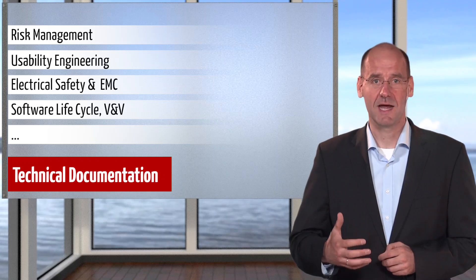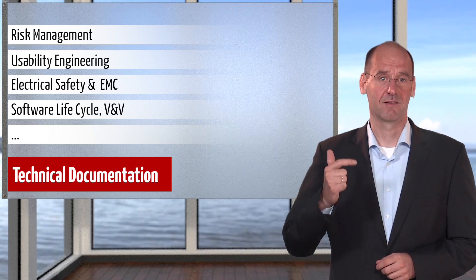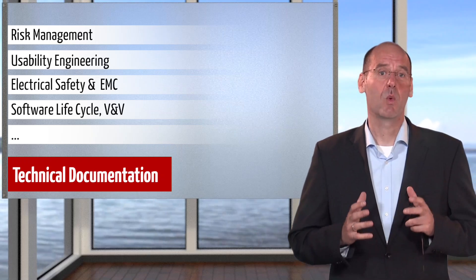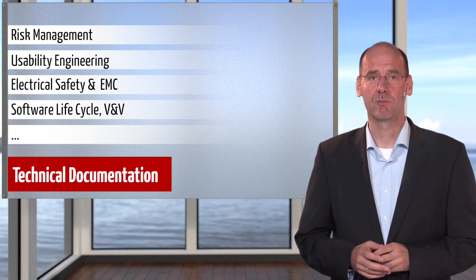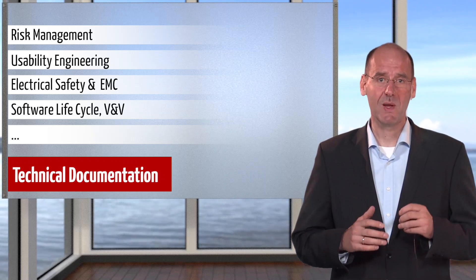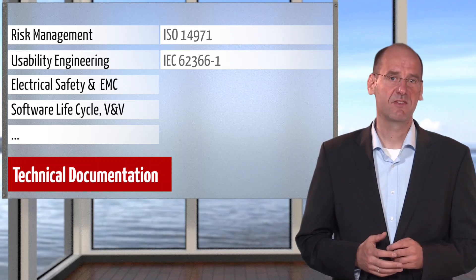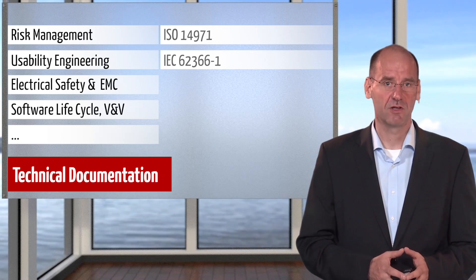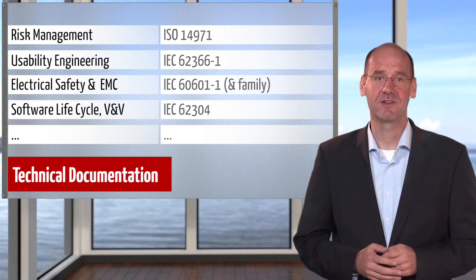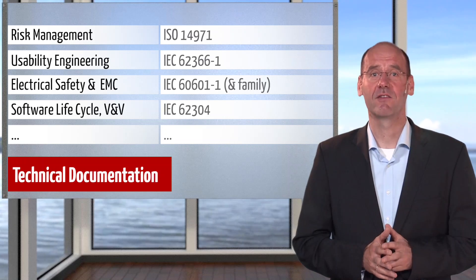To give manufacturers guidance on how to perform proper risk management or usability engineering, the medical device regulation, the MDR, provides two instruments to prove compliance: first, the harmonized standards, and second, the common specifications. As of releasing the MDR, there was neither a standard harmonized nor a common specification released, but it is more than likely that this is going to happen. For example, we expect ISO 14971 being harmonized for risk management, IEC 62366-1 for usability engineering, IEC 62304 for software, and the IEC 60601 family for medical electrical devices.